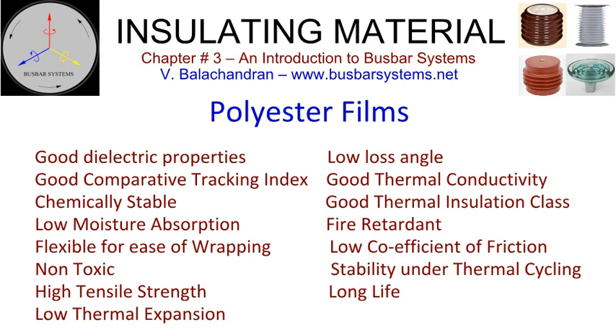Mylar is the most commonly used insulation in sandwich busways. It is the trade name for BOPET, biaxially oriented polyethylene terephthalate. The films are available in thickness varying from 12 micrometers to 500 micrometers, that is 0.012 mm to 0.5 mm.